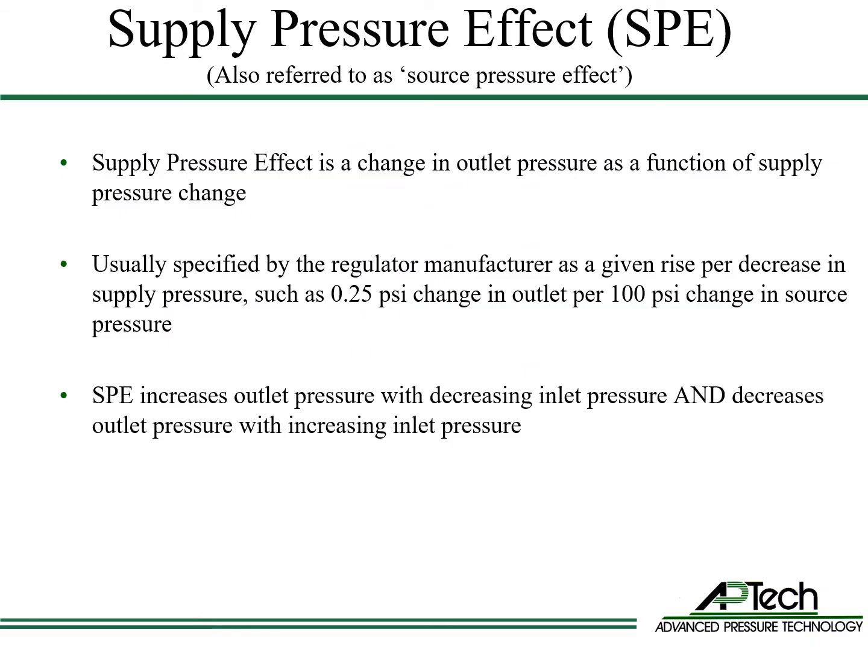Supply pressure effect is a change in outlet pressure as a function of supply pressure change. This effect is usually specified as the change in outlet pressure per change in inlet pressure — for example, 0.25 psi change in outlet pressure per 100 psi change in inlet pressure. Normally, supply pressure effect is encountered when the inlet pressure decreases as gas cylinders are consumed. As a result, outlet pressure increases as a gas cylinder is consumed. However, the supply pressure effect works with both decreasing and increasing inlet pressure. An increase in inlet pressure will cause a decrease in outlet pressure at the same rate as specified.